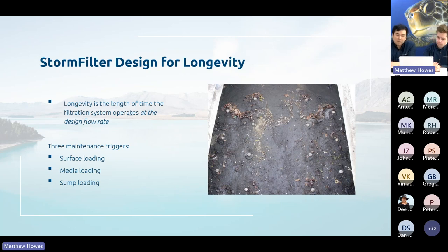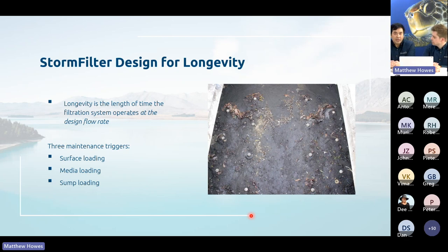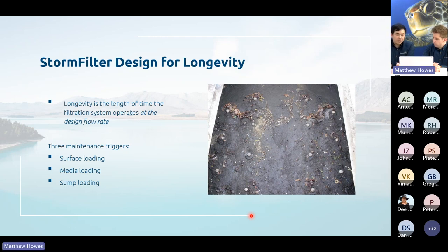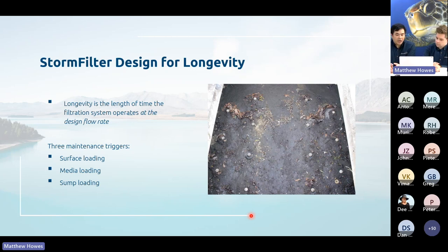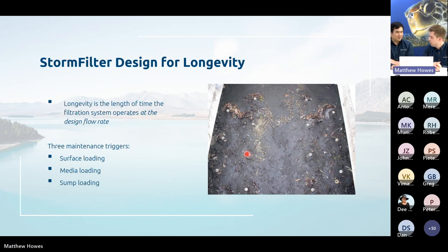A treatment device needs longevity before it needs to be maintained — that is, the length of time or amount of sediment it can handle while operating at its design flow rate. Once performance drops below that design flow rate, maintenance is required. We look at either the surface loading on the cartridges through the media, or how much sediment is in the sump. In a photo example, you can see the top caps of a Storm Filter that is well and truly ready for maintenance.